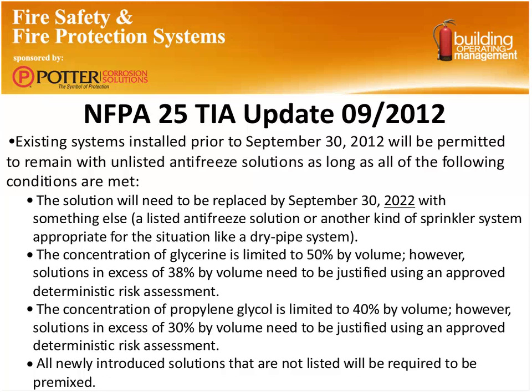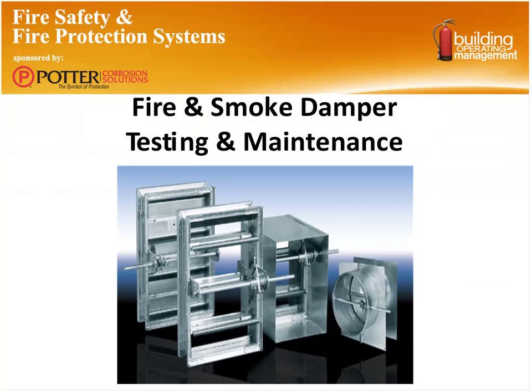I think the point here is that we would recommend that you at least have an understanding of the systems and try to make sure you work with your sprinkler contractor to determine how it is they're maintaining those, and make sure that there are not systems that have really high concentrations of the propylene glycol or the glycerin mix in those freeze-protected systems. So that kind of wraps up our little update on freeze protection systems, and we'll move to our next piece, which is fire and smoke damper testing and maintenance.